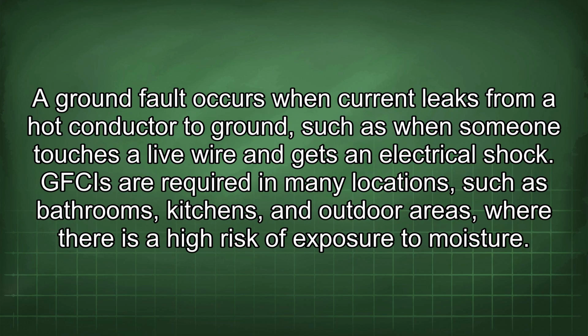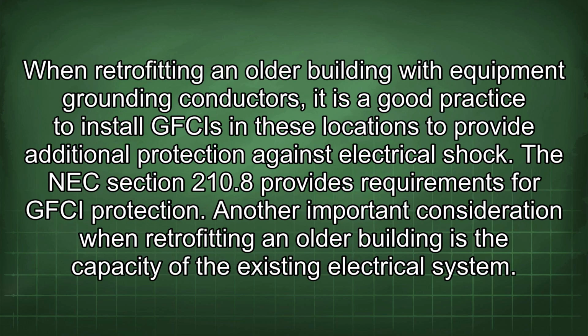A ground fault occurs when current leaks from a hot conductor to ground, such as when someone touches a live wire and gets an electrical shock. GFCIs are required in many locations, such as bathrooms, kitchens, and outdoor areas, where there is a high risk of exposure to moisture. When retrofitting an older building with equipment grounding conductors, it is a good practice to install GFCIs in these locations to provide additional protection against electrical shock.